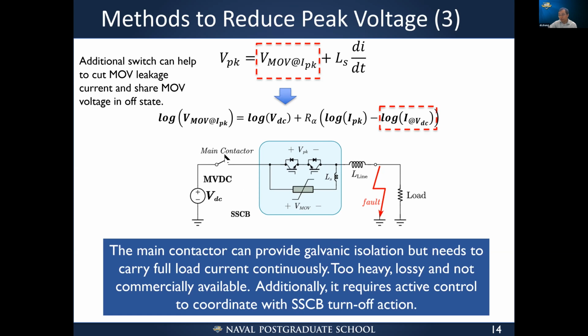If you turn off too early, you are cutting the current, right? So it's not a contactor, it's going to become a breaker, and we know that's very challenging and not doable. Or if you turn off too late, the MOV has already carried the high leakage current for too long, and the MOV will be damaged. So this is really challenging, as it requires active control.